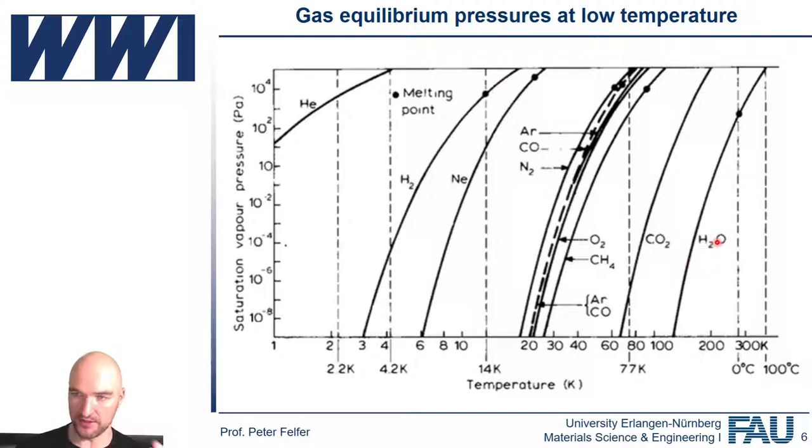Because if you open your system to ambient pressure, what is going to happen is that you get essentially a monolayer of water vapor condensing into your chamber or whatever you've opened up. And once you pump it down, it can take very, very long for the water vapor to leave.